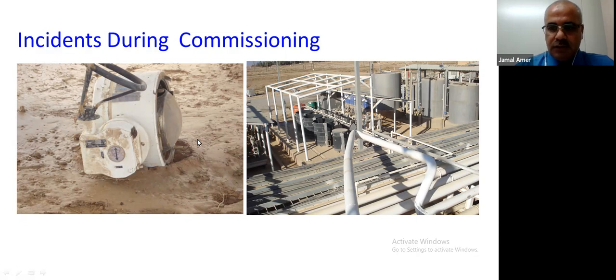What happened? Some mistake happened. One mistake happened. Even though all the commissioning controls and valves were covering everything, in the last minute somebody changed the position of this valve from the open position to the closed position.